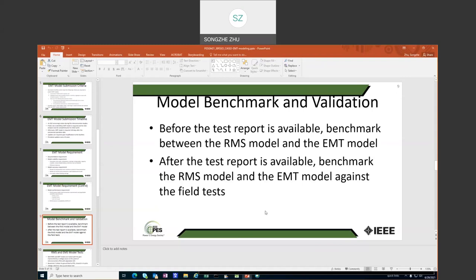We collect all the data, then the very important thing for the ISO to perform is to benchmark and validate the models. The test reports per NERC standards will be provided 12 months after the commercial operation of the generators. But our model requirement is 120 days after the commercial operation. So for some time, we do have the models, but we don't have the test reports. Before we have the test reports, we will benchmark between the RMS model and the EMT model. Then when the generation owner submits the test report to us, we will benchmark both the RMS model and the EMT model against the field test.